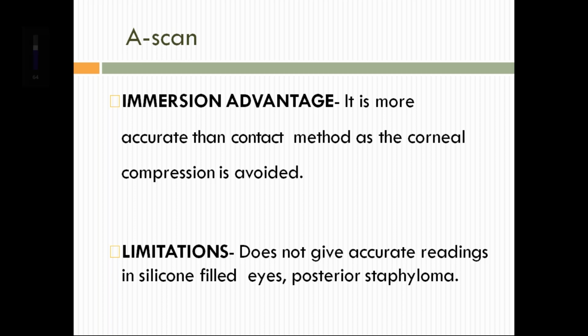Immersion advantage. It is more accurate than the contact method, as corneal compression is avoided. The limitation is that it does not give accurate readings in silicone-filled eyes or posterior staphyloma.